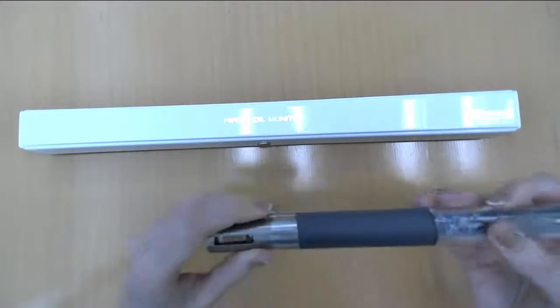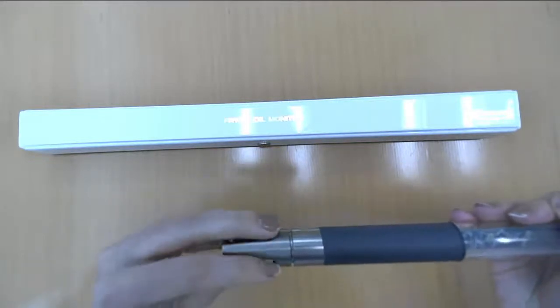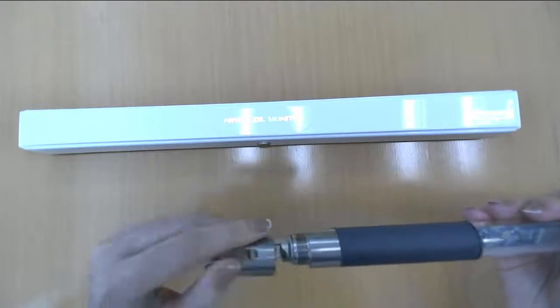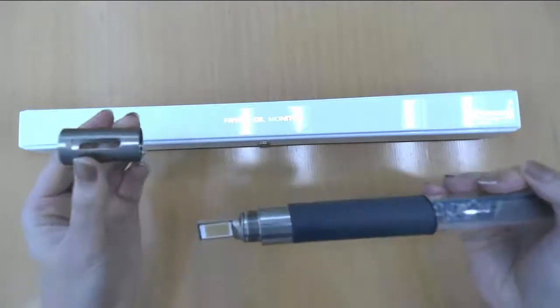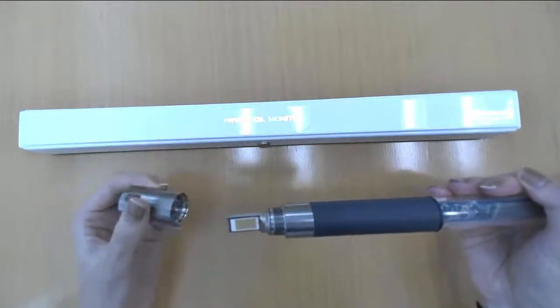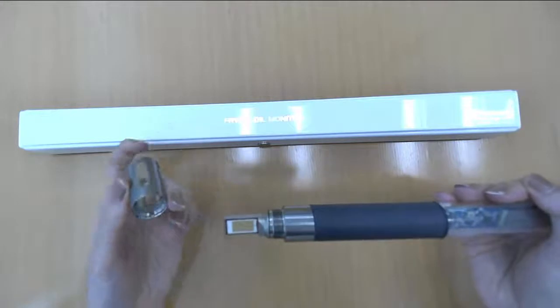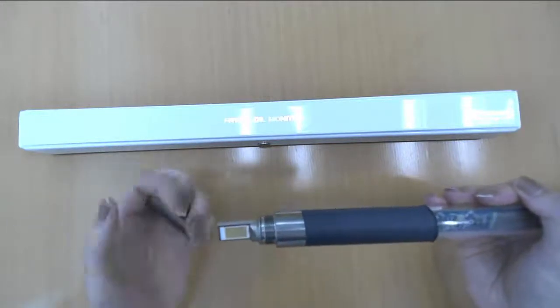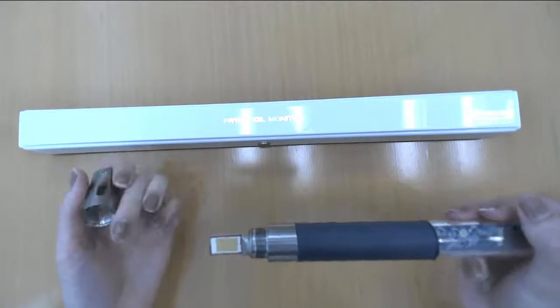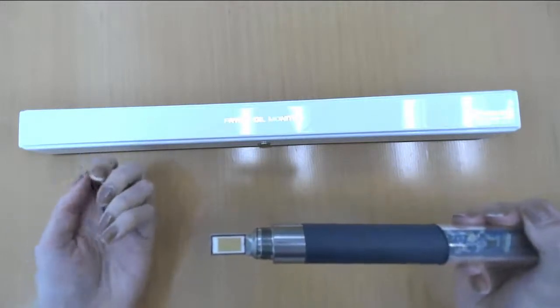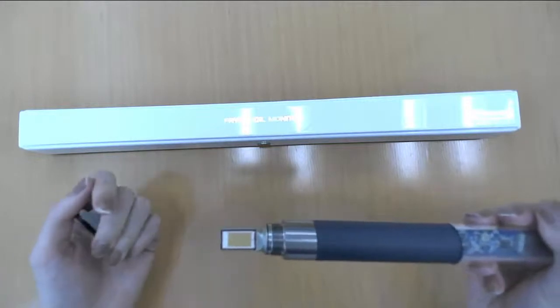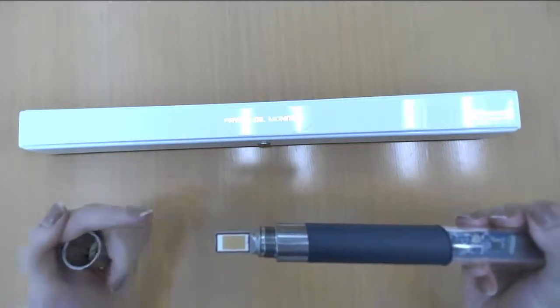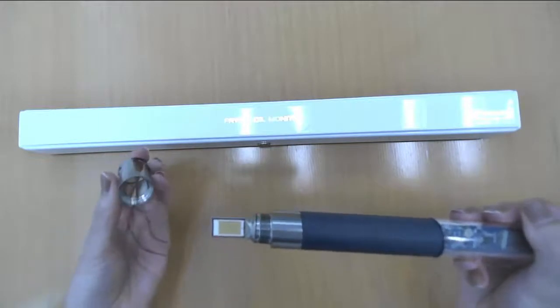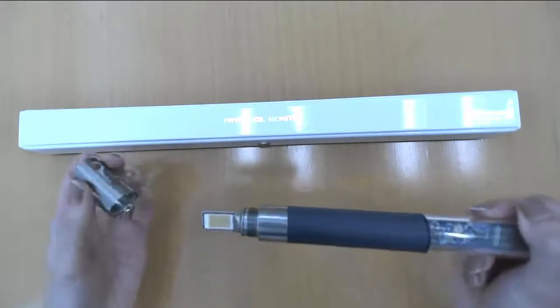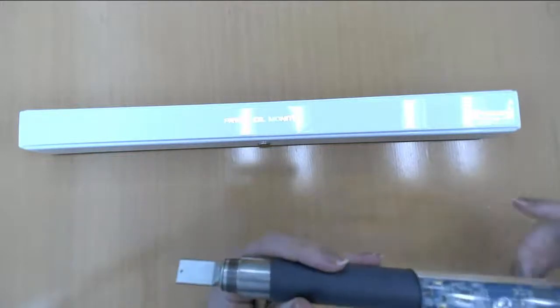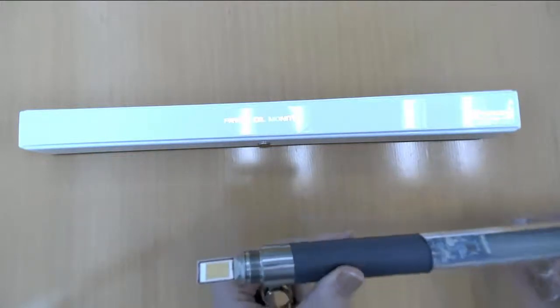And then when we move down, we have our sensor electrode. This is the sensor cover. It comes off really easily just by unscrewing it. If you want to do some deep cleaning, you can unscrew this and wipe with a soft cloth. Especially with oil, you might find that just wiping it off with some water is not enough, so you can actually use some mild soap to clean this whole area as well. I would recommend cleaning it every so often so that you can have more accurate measurements and not a gross instrument.